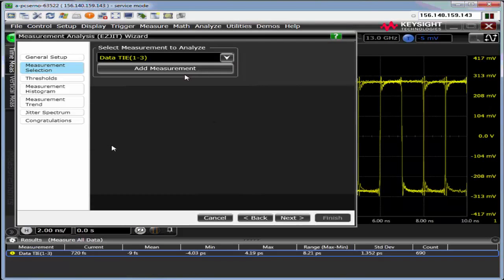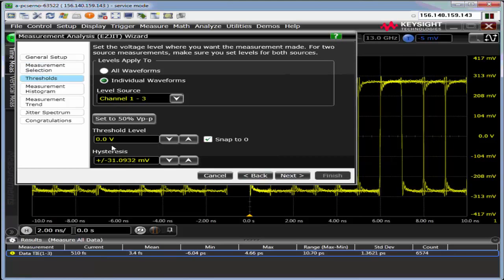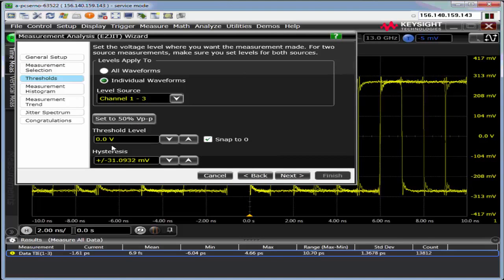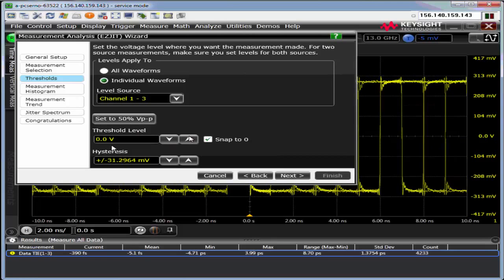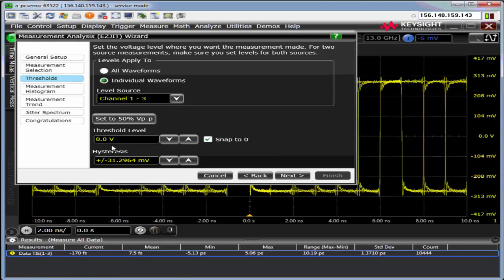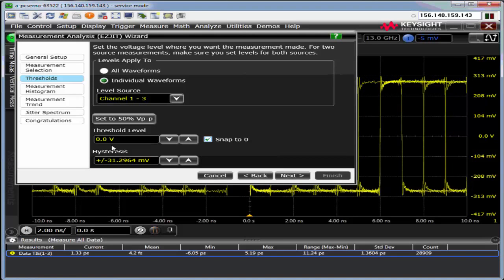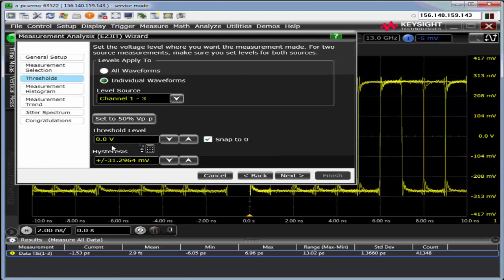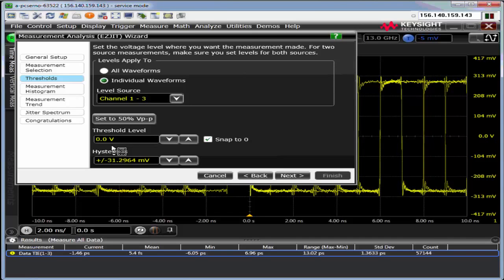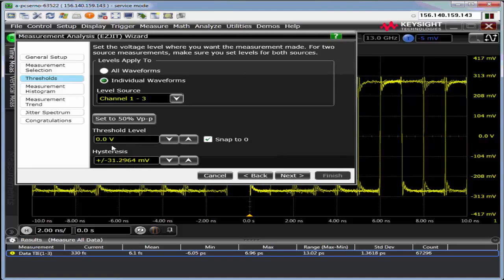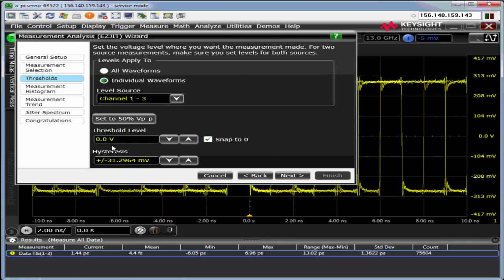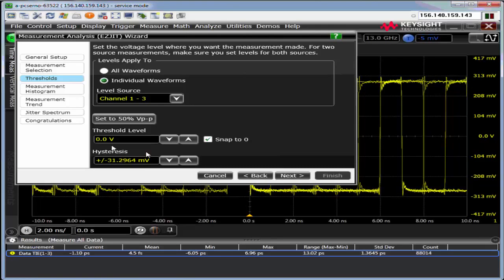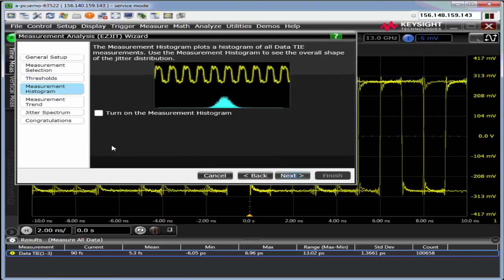I've got my data TIE measurement on channel one minus three, set to 50% peak to peak. If you have this snap to zero checked, it will force it to a zero threshold if the threshold is found to be within plus or minus 10 millivolts of zero volts. Hysteresis basically says the signal has to go through minus 31 to plus 31 millivolts. So if it doesn't have at least 62.36 millivolts swing, it doesn't count as an edge.